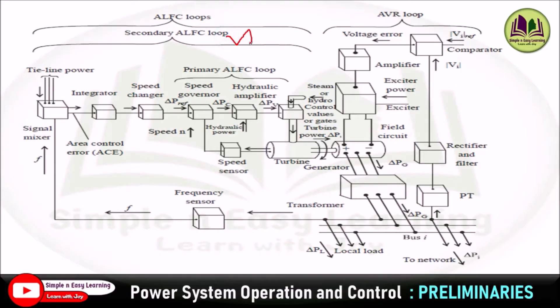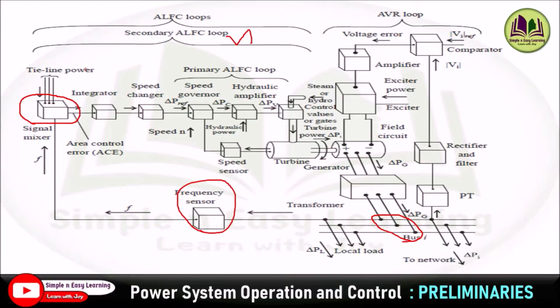The second is the secondary ALFC loop. In this loop, a frequency sensor senses the frequency at the bus bar directly. This frequency is compared with the tie line power frequency. The tie line is the line where frequency and voltage remain constant, so that frequency is taken as the reference frequency. The actual frequency from the frequency sensor is compared with the reference frequency in a signal mixer, and the output of this signal mixer is the error frequency, called the area control error (ACE). The ACE is sent to the speed changer through an integrator. The integrated signal is sent to the speed changer, which gives the reference speed to the speed governor, and then the primary ALFC loop continues its operation.